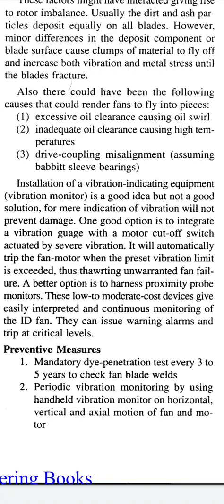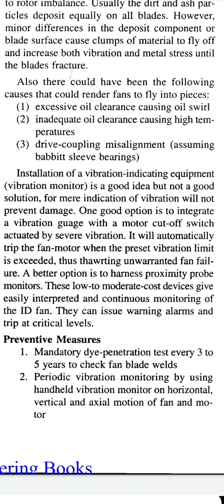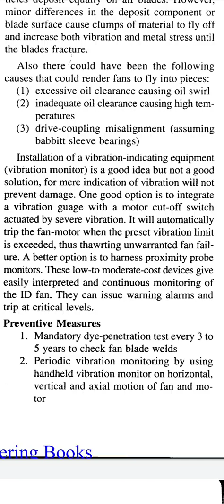One good option is to integrate a vibration switch with a motor cutoff switch actuated by excessive vibrations. It will automatically trip the fan motor when the preset vibration limit is exceeded, thus preventing unwarranted fan failure. A better option is to harness proximity probe monitors. These low to moderate cost devices give easily interpreted and continuous monitoring of the ID fan. They can issue warning alarms and trip at critical levels.